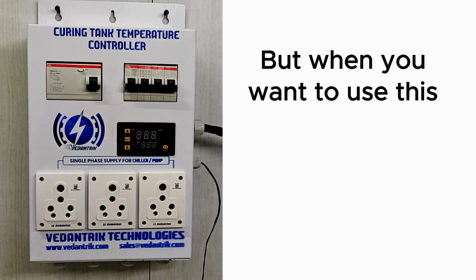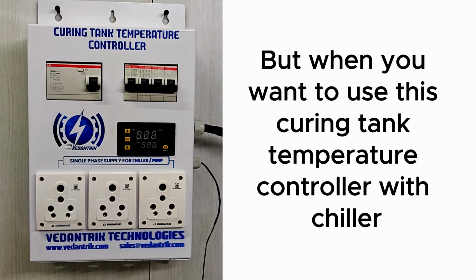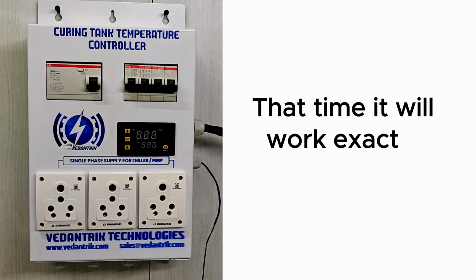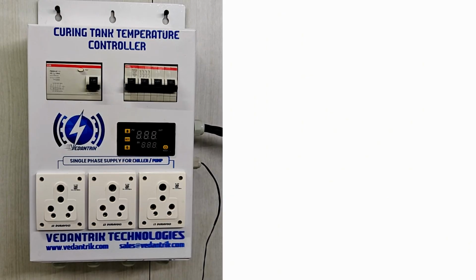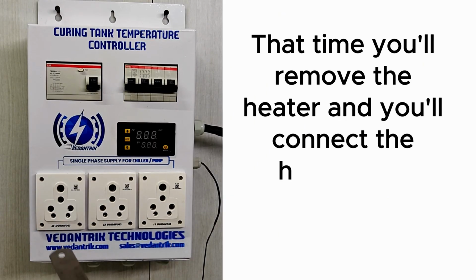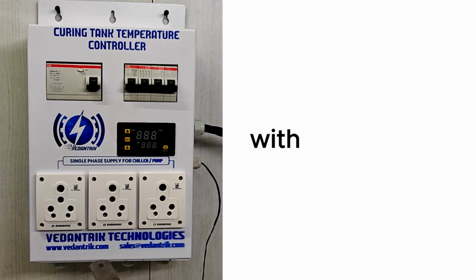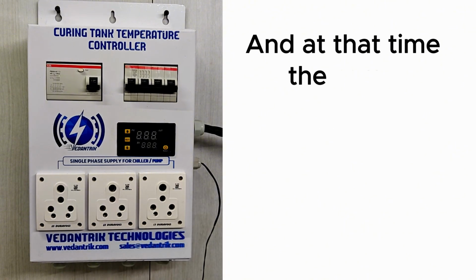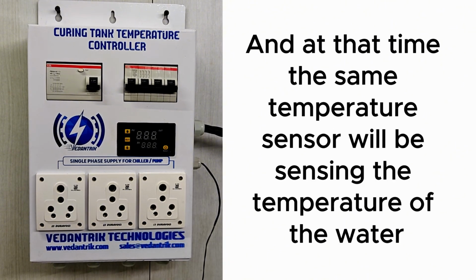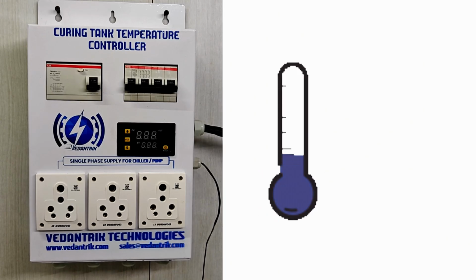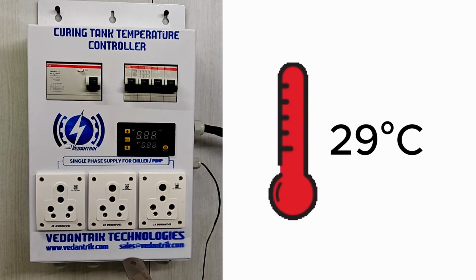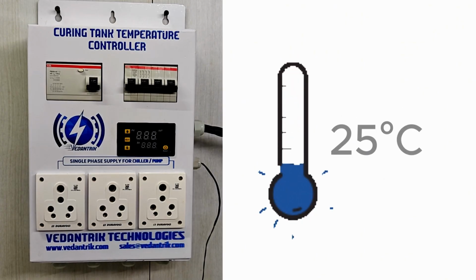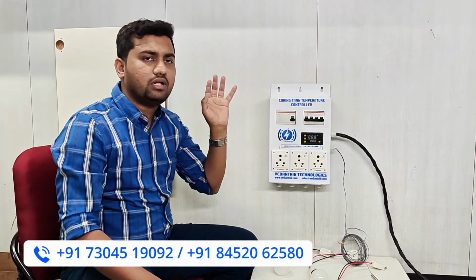But when you want to use this curing tank temperature controller with a chiller, it will work exactly opposite. At that time you will remove the heater and connect the chiller with the system, right? And the same temperature sensor will be sensing the temperature of the water. If the temperature goes above 29 degrees Celsius, the chiller will be on. If the temperature goes below 29 degrees or 25 degrees Celsius, the chiller will be off. So till now we understand how the curing tank temperature controller works and what it is.